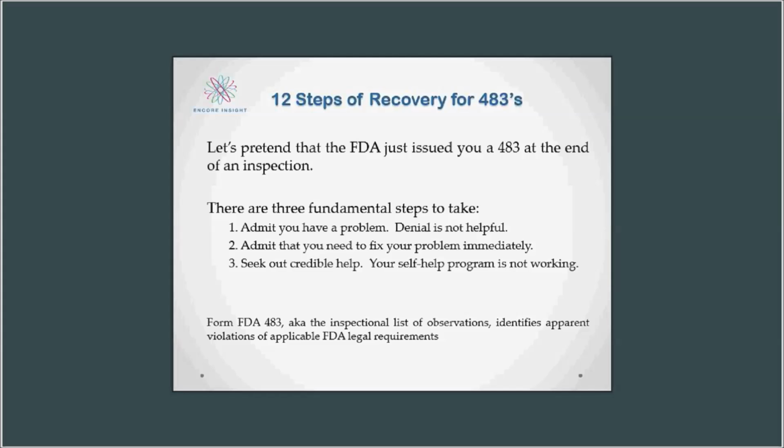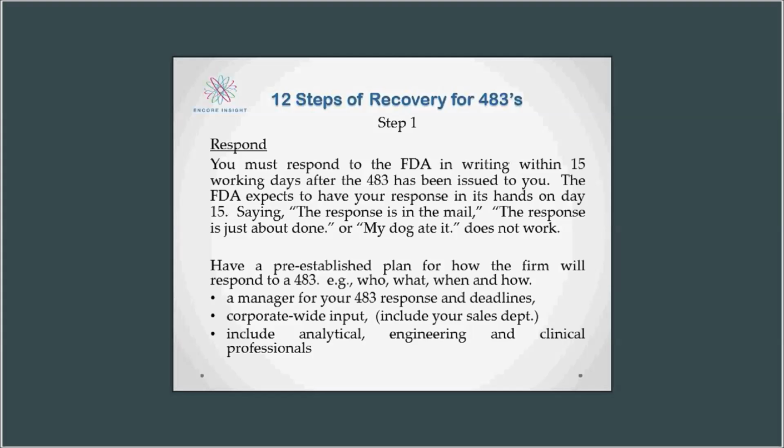You have a problem, you need to fix your problem, and you want to check out how you were able to do that. So let's go into the first step of a 12-step recovery program for FDA 483s. First, you have to respond. This is really important because FDA is fussy about this. You have to respond to the 483 within 15 days after the 483 was issued to you.